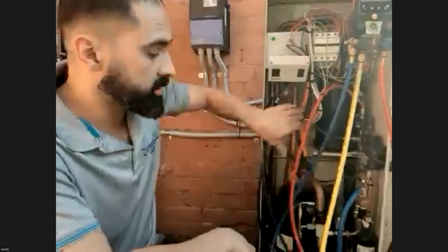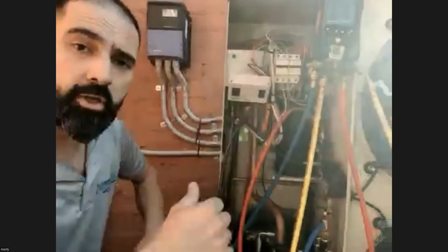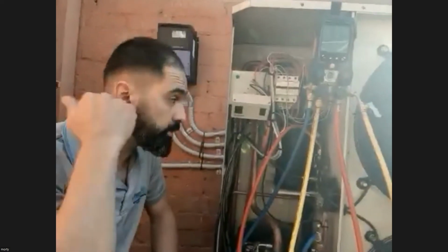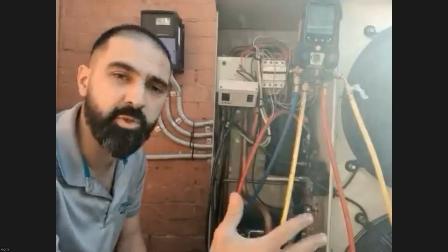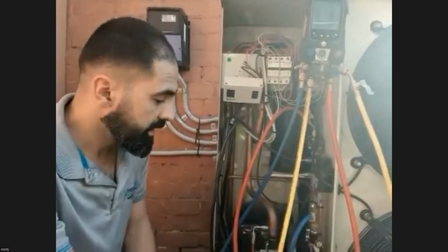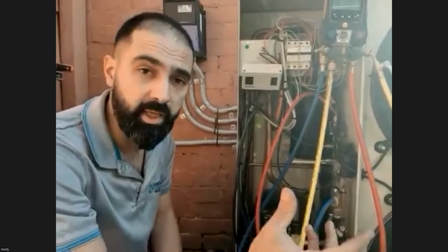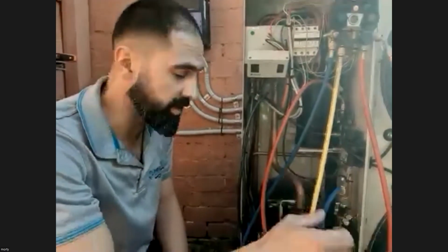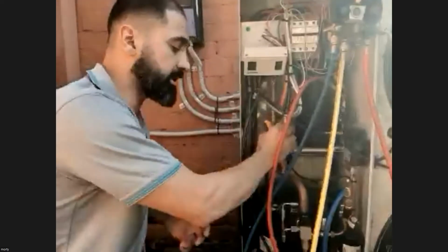A lot of people will grab this sensor here and go, for example, about a meter back here, that's my suction right there. If you've got liquid coming back through into the accumulator, you'll definitely get a completely different reading, almost 5 to 7K different. That 5 to 7K would throw the system completely off if you are sitting on the limits of the case itself. So what I normally like to do is always get it right at the entry.